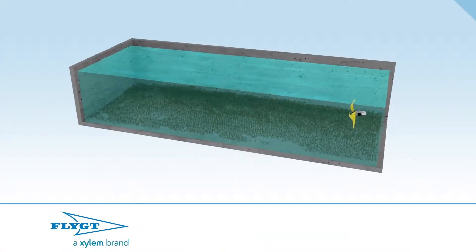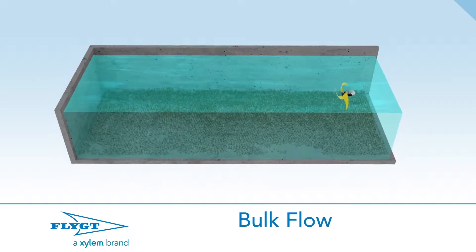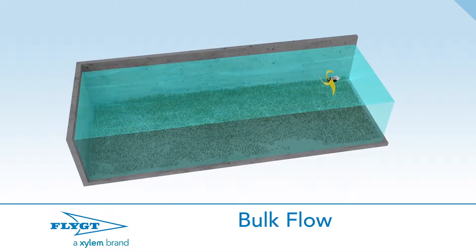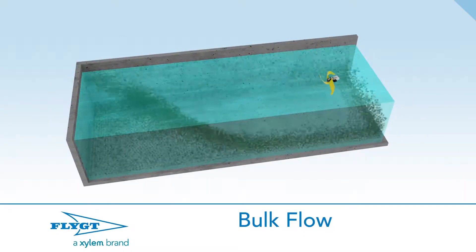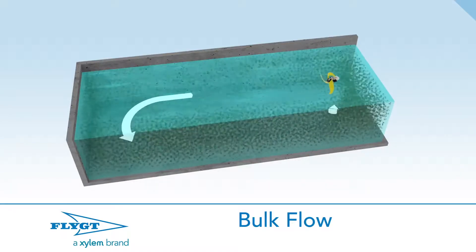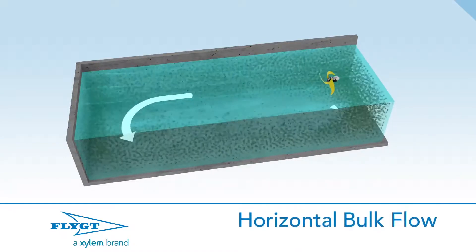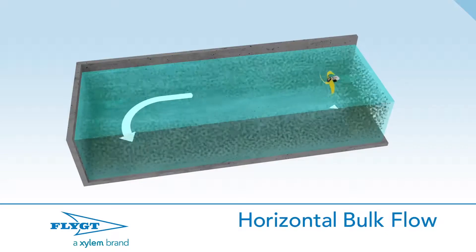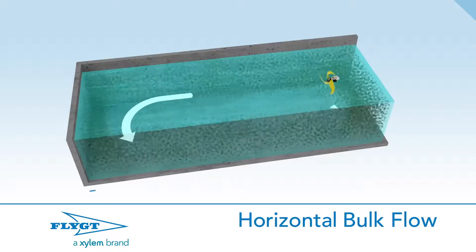Before sizing a mixer, you need to understand bulk flow. Bulk flow is the movement of the entire tank's content in a regular pattern. Creating bulk flow is the most efficient way to keep a tank mixed. Most tanks can support a variety of bulk flow patterns, but it's easiest to create bulk flow around the tank's longest axis.